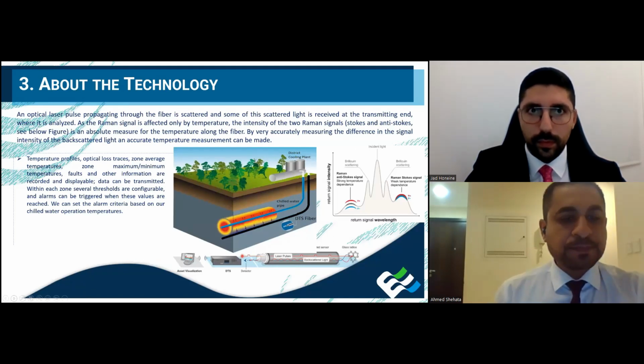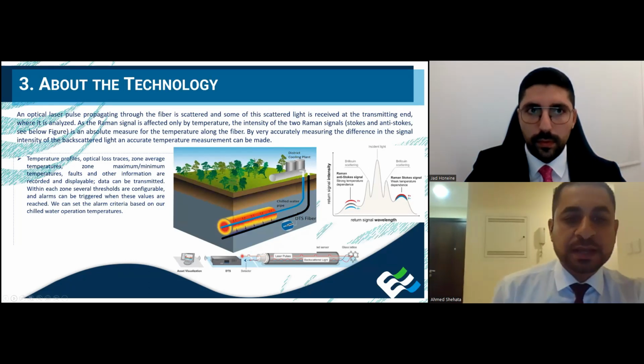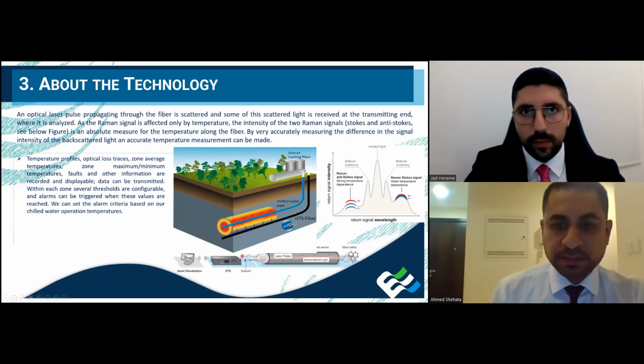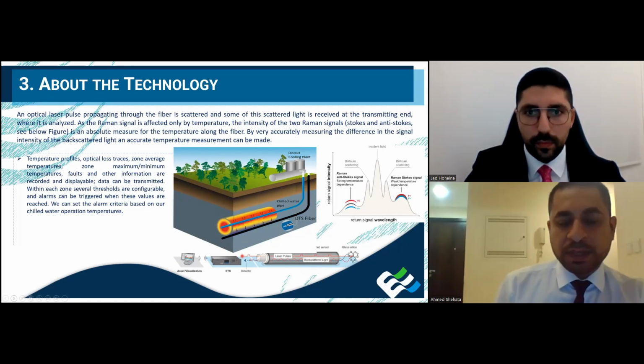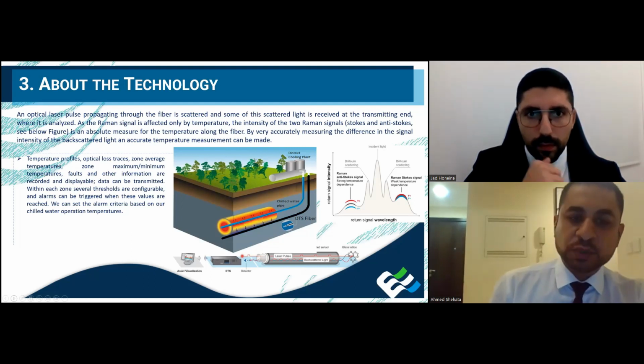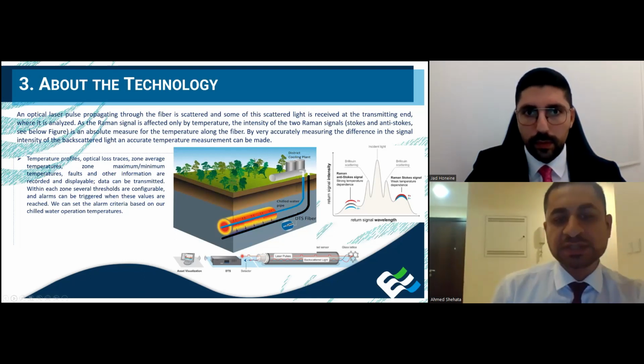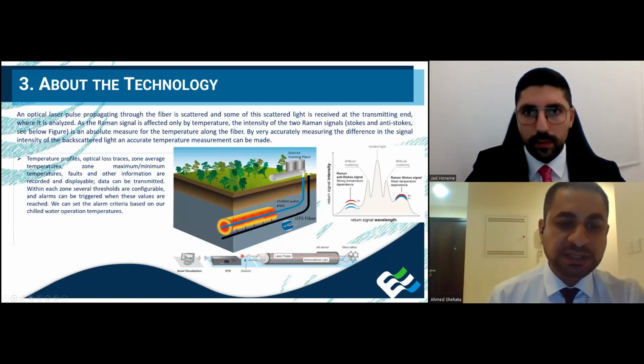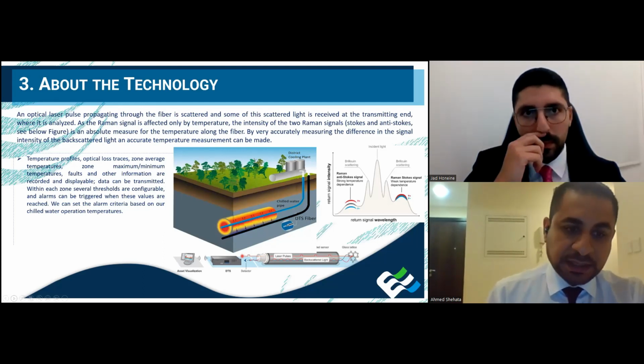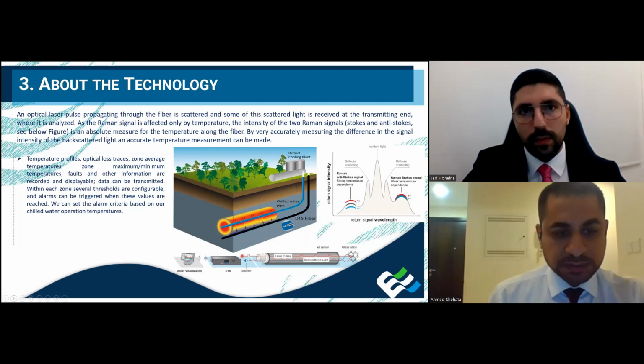I will explain how the DTS system works. DTS stands for Distributed Temperature Sensor. We utilize the fiber optic cable with high accuracy to determine temperature. This distributed temperature sensor is able to sense temperature over a long range with accuracy of plus or minus 1 degree Celsius. This system is composed of 2 parts.